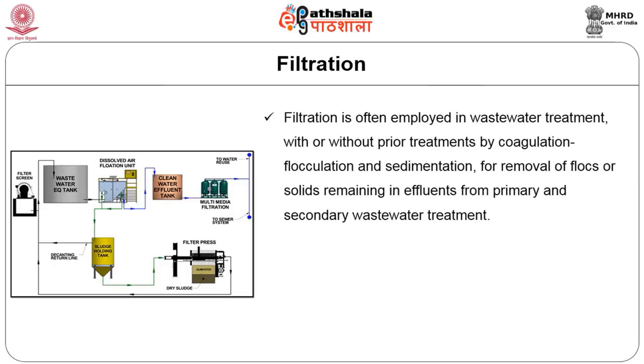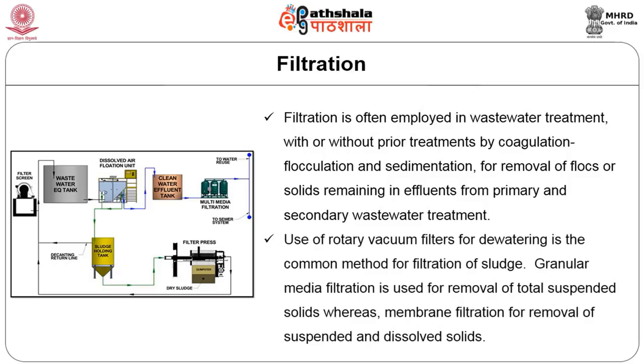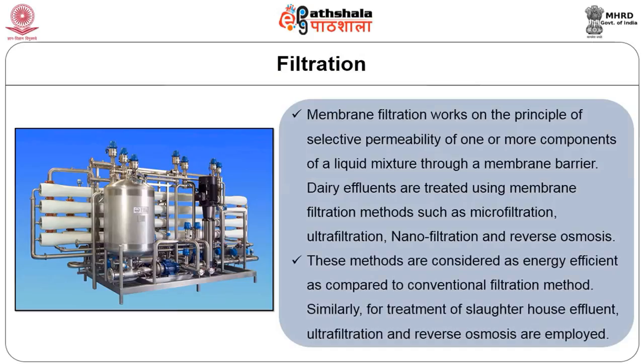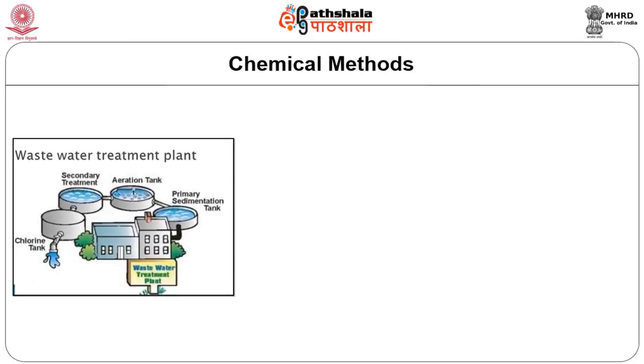Filtration is often employed in wastewater treatment with or without pretreatments by coagulation, flocculation, and sedimentation, for removal of flocs or solids remaining in effluents. Use of rotary vacuum filters for dewatering is the most common method of sludge filtration. Granular media filtration is used for removal of total suspended solids, whereas membrane filtration is for removal of suspended and dissolved solids. Membrane filtration works on the principle of selective permeability through a membrane barrier. Dairy effluents are treated using membrane filtration methods such as microfiltration, ultrafiltration, nanofiltration, and reverse osmosis. For treatment of slaughterhouse effluent, ultrafiltration and reverse osmosis are employed.